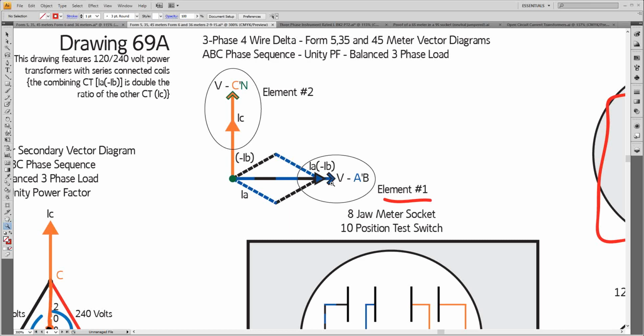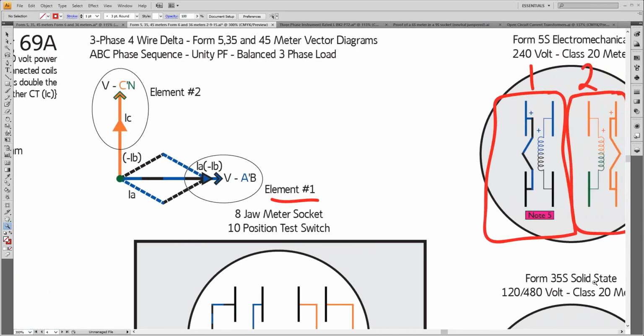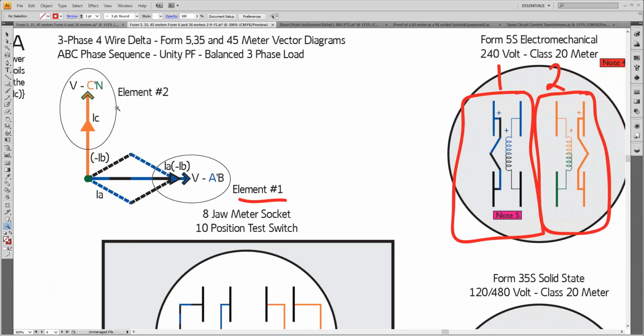This current and that voltage sitting right in phase is what's happening inside of this meter element. So current through that current coil, the summation current, with A to B voltage across that potential coil. In the other element now, we have a second CT that has IC current in it. IC current is the current that's going to flow through this current coil here, with C to neutral voltage across our potential coil.